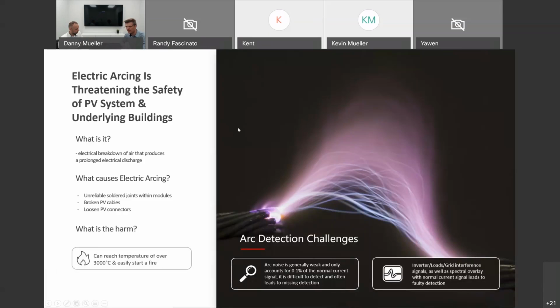Exactly. Now we want to talk a little bit about some other features which are very common and required in the North American market. They're not so much required or not at all required in the rest of the world. And AFCI, for example, the arc fault circuit interruption, is one of them. And arc fault in the past, when it was introduced under the National Electric Code in the States in 2014, was a little bit of pain because there were a lot of not fully developed arc fault detection systems in the market from multiple manufacturers, and that led to many people having issues with AFCI fault trips, and it didn't work the way it was promised, or it had issues at very cold temperatures from an electric noise perspective.